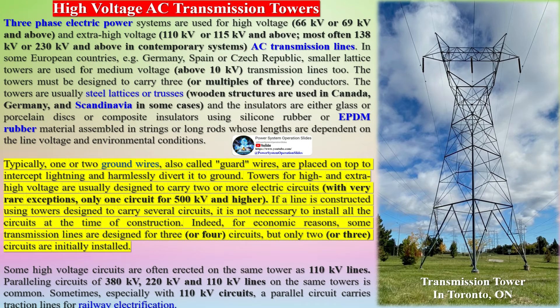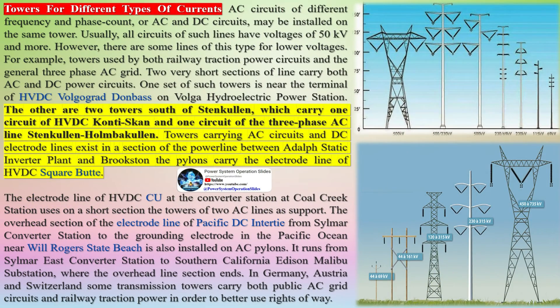Three-phase electric power systems are used for high-voltage (66 kV or 69 kV and above) and extra-high-voltage (110 kV or 115 kV and above, most often 138 kV or 230 kV and above) AC transmission lines. In some European countries such as Germany, Spain, or Czech Republic, smaller lattice towers are also used for medium-voltage (above 10 kV) transmission lines. These towers must be designed to carry three or multiples of three conductors.